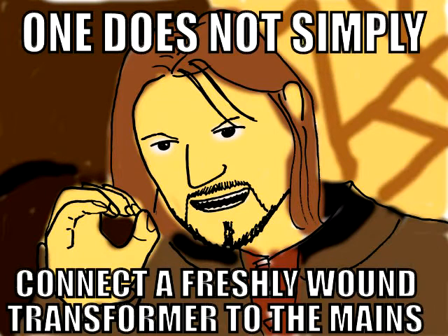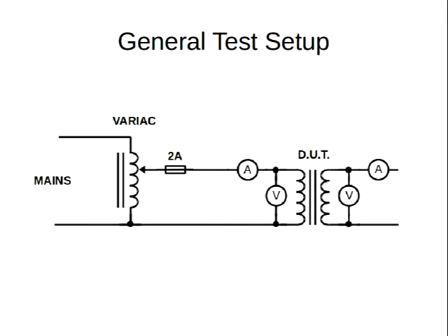Because one is never sure how it will behave, one does not simply connect a freshly wound power transformer to the mains. Our general setup for testing comprises a variac for raising the primary voltage gradually while monitoring currents and voltages, a current limiter and various meters.